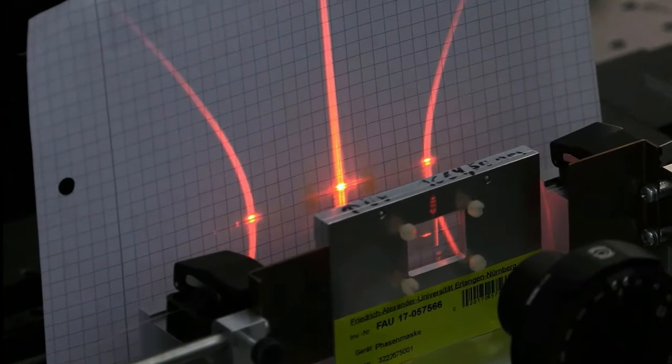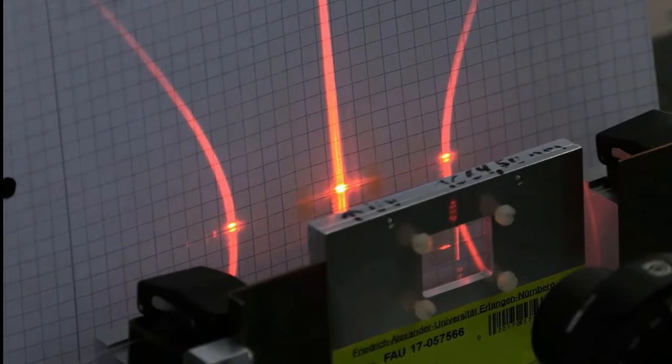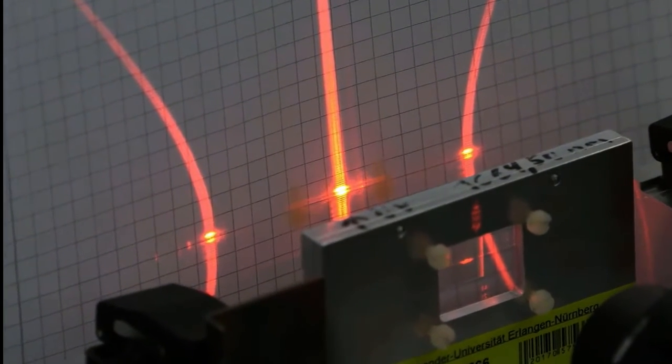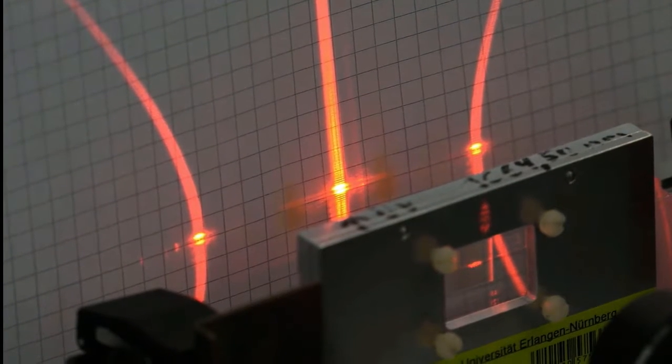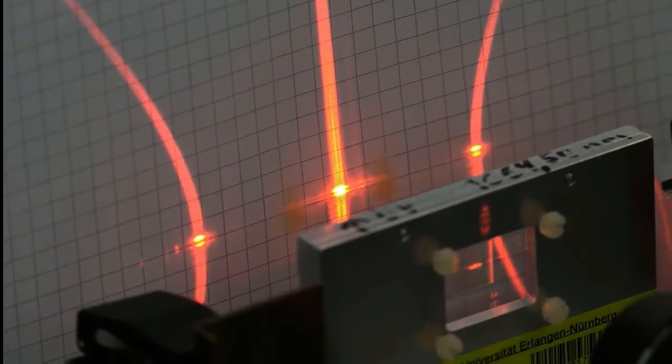Now we only need to check the height of the fiber with the pilot laser. If the bright spots above and below the fiber appear the same size at the screen, we hit exactly the middle of the fiber. This looks really good.